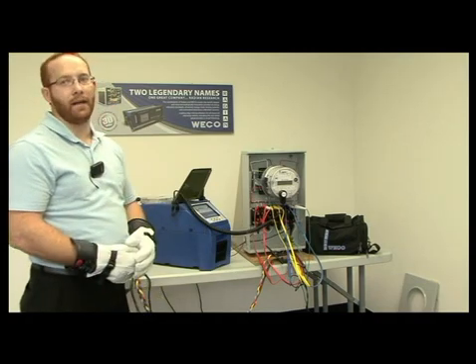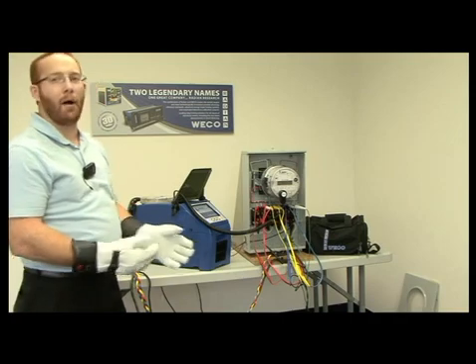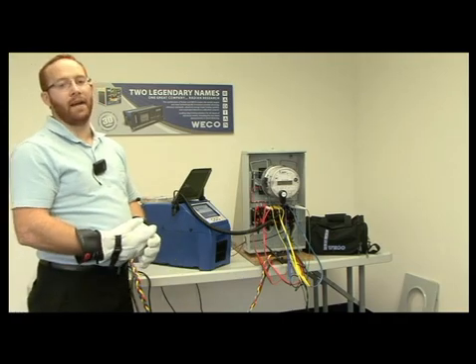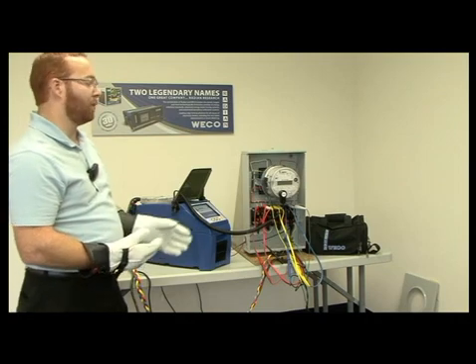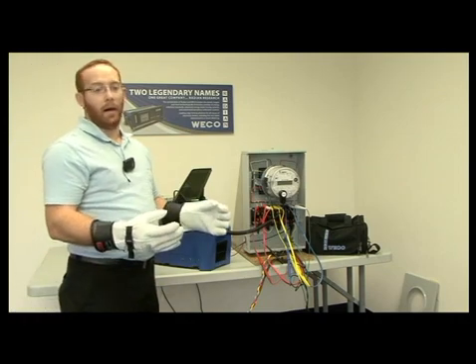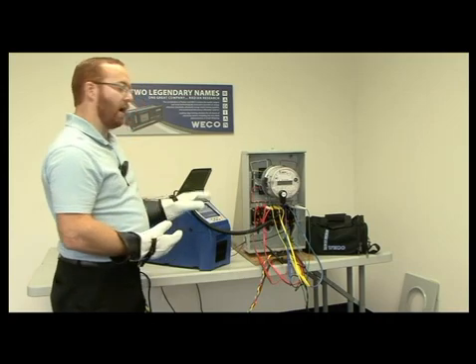And that will be the first test point. The second test point after this test is done will be a power factor at 2.5 amps. And then lastly, once that test is complete, it will perform a light load at 0.25 amps. And it's going to be a fully automated test.